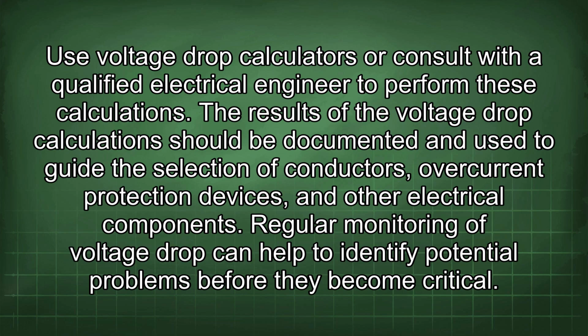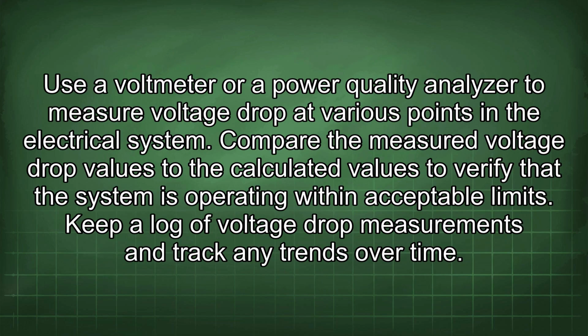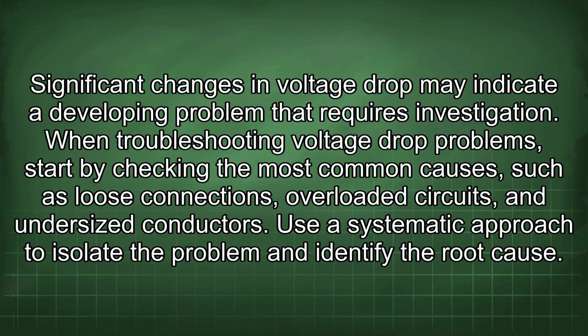Regular monitoring of voltage drop can help to identify potential problems before they become critical. Use a voltmeter or a power quality analyzer to measure voltage drop at various points in the electrical system. Compare the measured voltage drop values to the calculated values to verify that the system is operating within acceptable limits. Keep a log of voltage drop measurements and track any trends over time. Significant changes in voltage drop may indicate a developing problem that requires investigation.